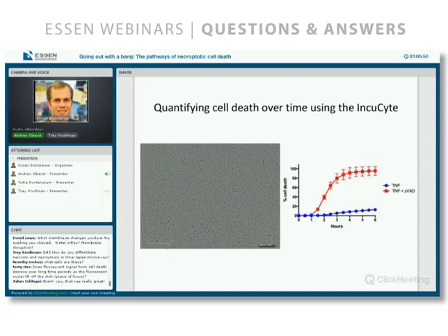Okay. A second question, related to this slide as well, comes from Terry. Does the fluorescent signal from cell death decrease over long periods as the fluorescent nuclei lift off the dish? That's a good question. One of the great things about the IncuCyte for all these assays is that the plates themselves, the cell dishes, don't move. You put them in a drawer and they stay still, and then the imaging head scans around to the different locations on the dish that you've identified.